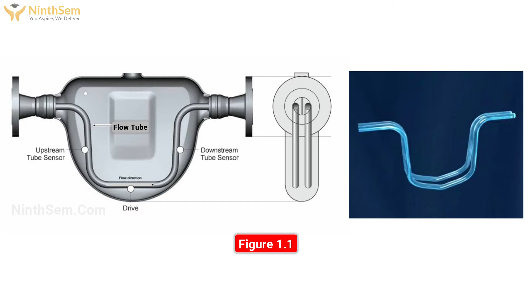As you can see in figure 1, there is an image of a Coriolis mass flow meter. Let us understand how the Coriolis mass flow meter works inside the mass flow meter body. In this figure you can see there is a tube. There is a tube having a U shape, fixed inside the flow meter body. In this tube, the fluid or gas whose flow rate is going to be measured is allowed to flow.